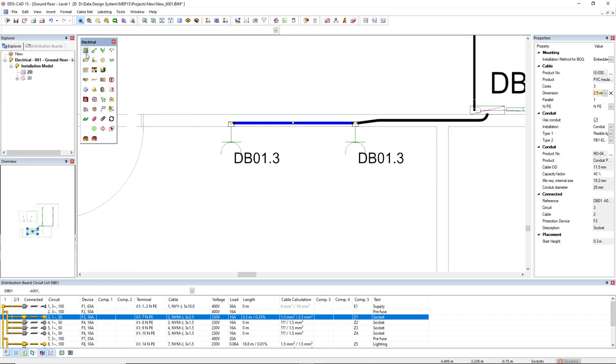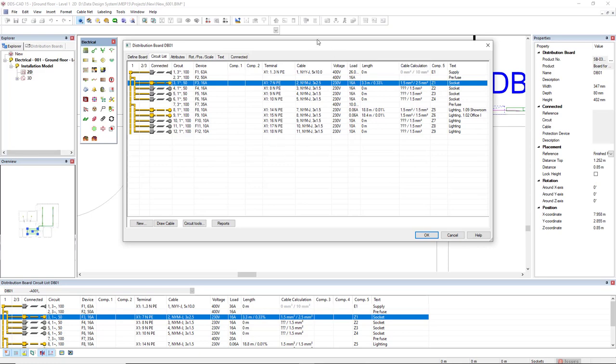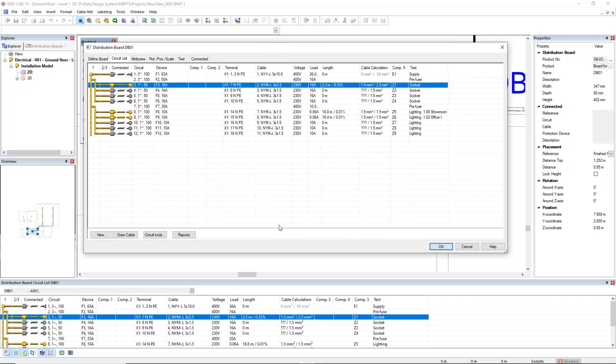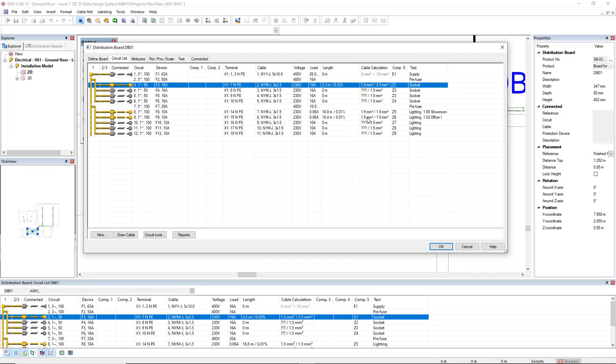Now, if we open the distribution board, just to have a better view of the circuit list, we see here that for these three circuits that we have correctly assigned the components, we see in the column length the length of the cable or the worst path when we have more than one route. And then we see on the right the voltage drop. We also have the column cable calculation. On the left we see the calculated cable cross section of the cable, and on the right the selected cable. I will double click this entry for the circuit number 3 so we can see more details.